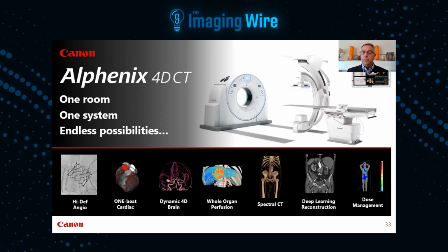And for the larger patients, and welcome to the United States, there are large patients here. For the larger patients, it might be difficult to not get a bit of cutoff on certain organs that you're trying to view. When you put that patient table into the CT scanner, you're going to get a very wide coverage, up to 50 centimeters of coverage, that's going to eliminate missing anything that you need. And you'll get the much better low contrast detectability of the CT scanner, plus the speed at which you can actually acquire that CT image.